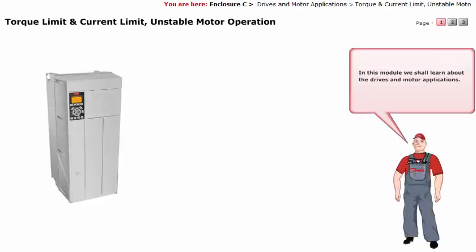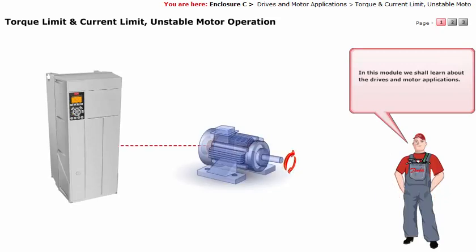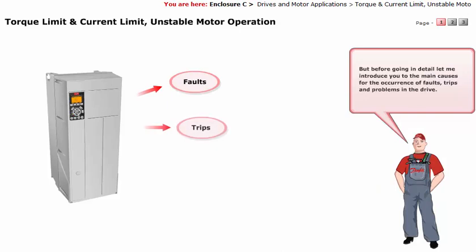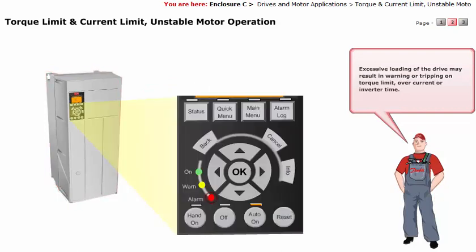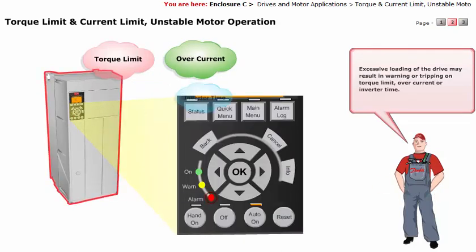In this module, we shall learn about the drives and motor applications. But before going into detail, let me introduce you to the main causes for the occurrence of faults, trips, and problems in the drive. Excessive loading of the drive may result in warning or tripping on torque limit, over current, or inverter time.